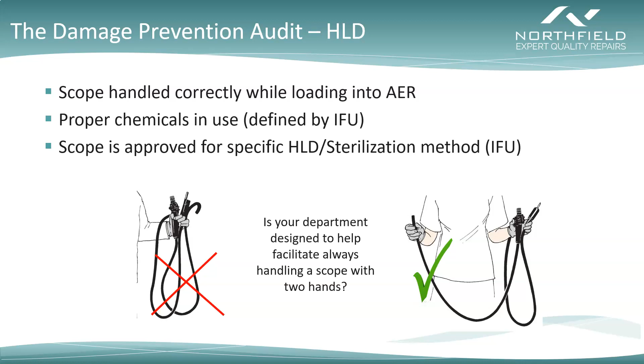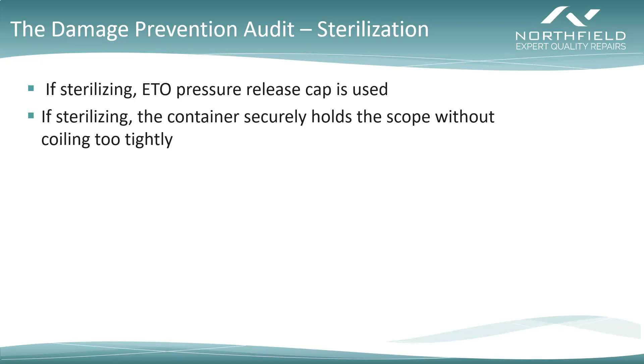Now, if you are sterilizing your scopes, for example, a cystoscope or your ureteroscope or some bronchoscopes, it's very important to make sure that that ETO pressure cap is being used. We also need to make sure that the container securely holds the scope but without coiling it too tightly. And this is when it's really important to make sure that you have a container that has been designed specifically to hold the scope that you are sterilizing. Very often, if you're just forced to make something work, it's not designed properly, and so it doesn't hold the scope properly, so it's rattling around, or maybe it's too small and it ends up having to bend the scope in a way that it's not really designed to in order to just make it fit. And that's where a lot of damage can occur. And you can see the kind of damage that can occur to a small diameter scope if you forget to put that cap on there, so it's very important.